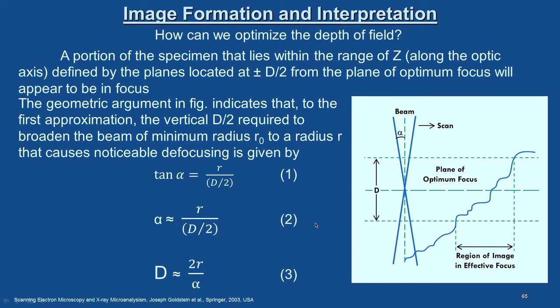An important feature of SEM is depth of field, which we discussed in earlier theory. How can we optimize depth of field? Looking at the schematic: the specimen surface has the beam falling on it; the plane of optimum focus is where the beam converges, defined by alpha. Assume a fracture surface with uneven ups and downs. A portion of the specimen that lies within the range Z along the optic axis, defined by planes at ±D/2 from the plane of optimum focus, will appear in focus.